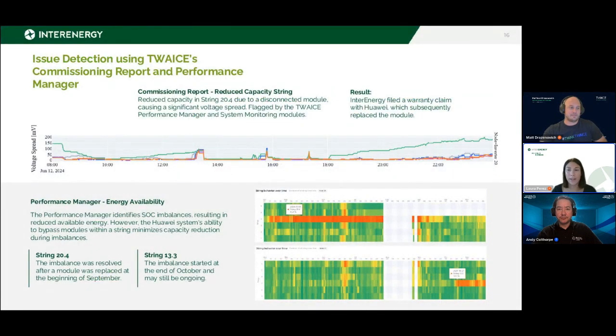I just want to highlight a couple of topics regarding the commissioning report. One is that the test for commissioning can be delayed. For example, in our case, we had some low solar resource days, so we weren't able to do a full cycle of charge and discharge of the batteries. Also, we needed to respect central dispatch times and needs, which delayed the report by some weeks. And most importantly for us, this report helped us make a claim to the manufacturer. As you can see in the image, we detected some misperformance, and they replaced the defective modules. Without this tool, we wouldn't have been able to detect that.